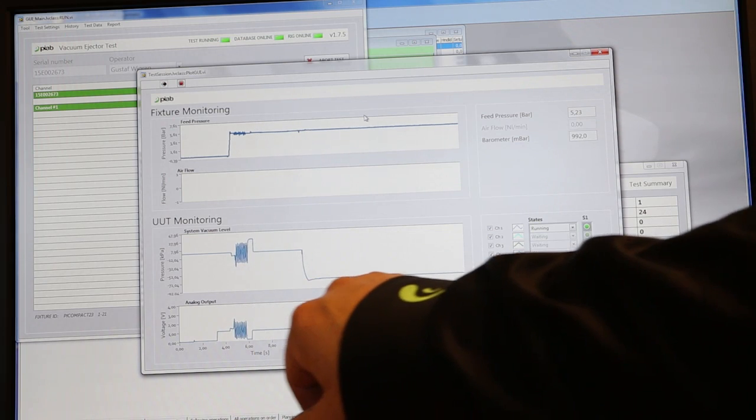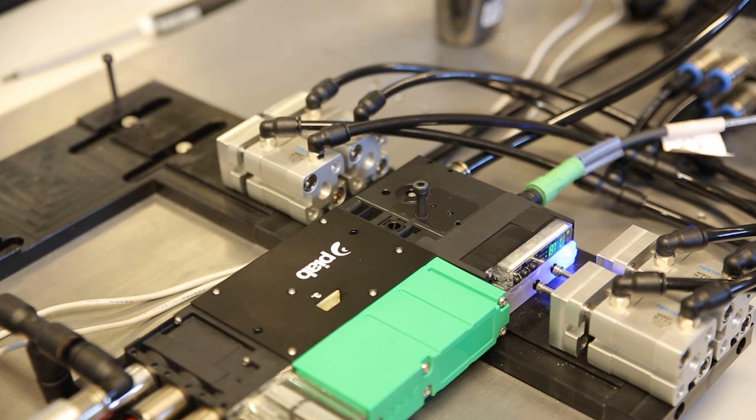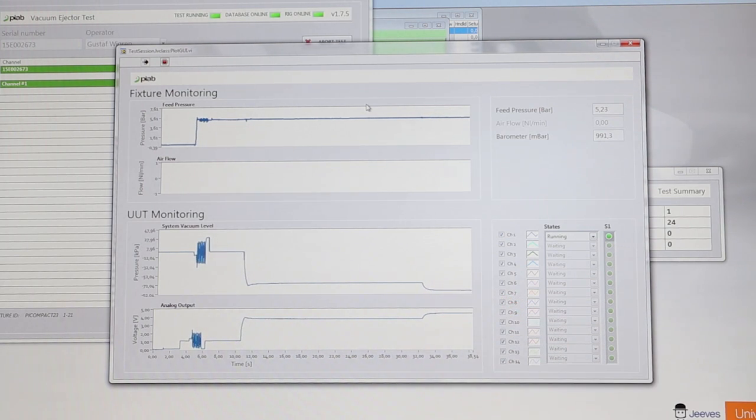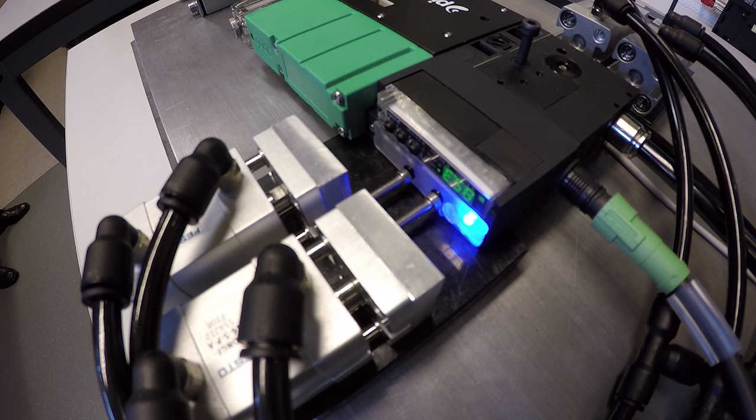pump is good or not in terms of flow, we do a sealed test to find out whether or not it's leaking vacuum or if we have made any mistakes in the assembly. After the sealed test, we go for a maximum vacuum test, where we test how deep a vacuum level the pump can actually obtain. And we finish off by doing a positive pressure and a blow off for the pump.